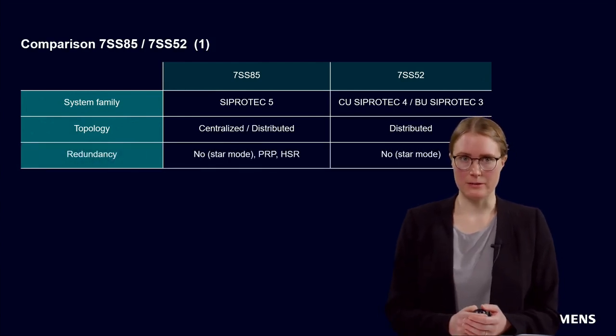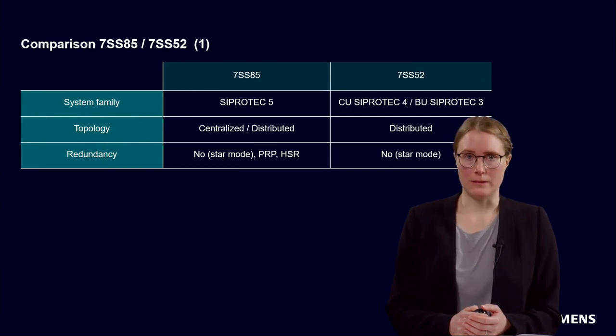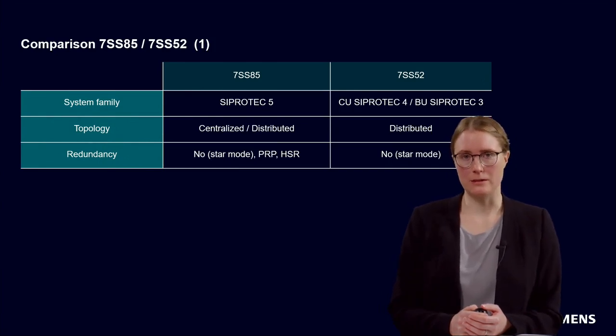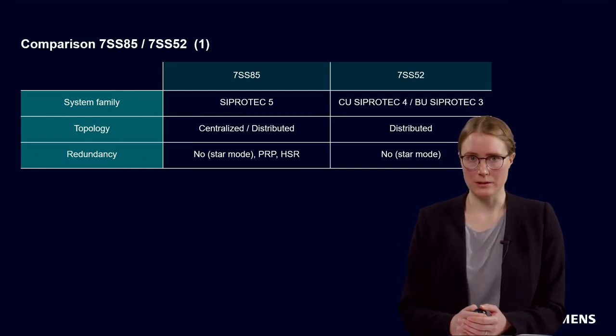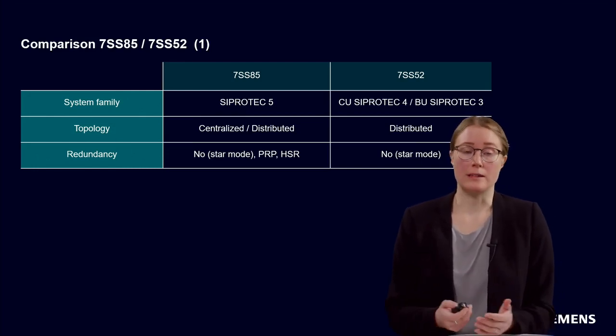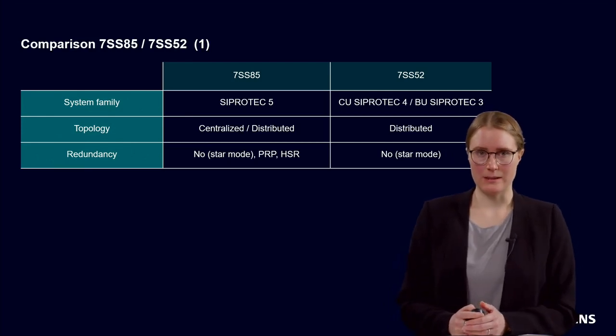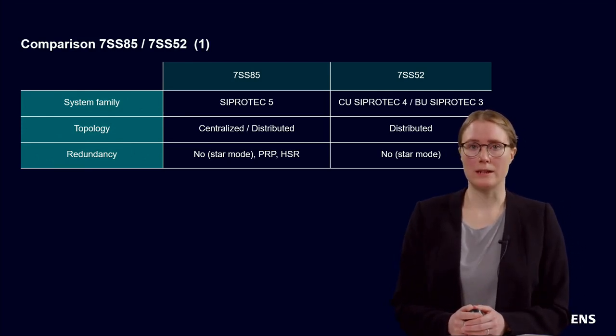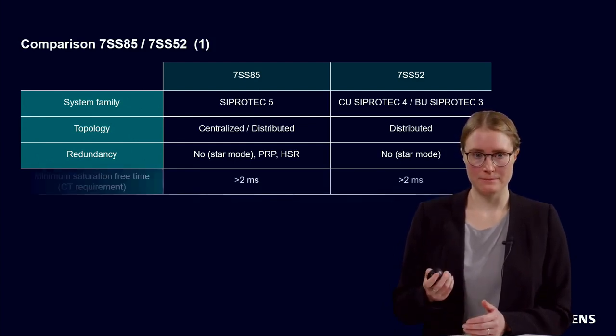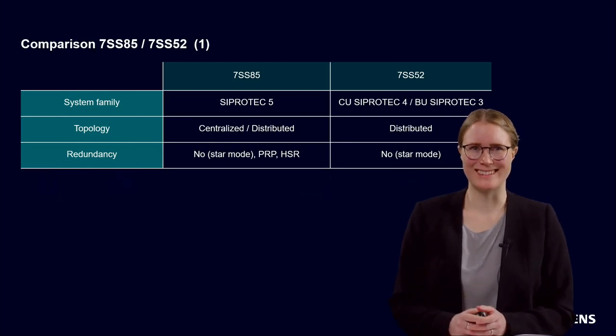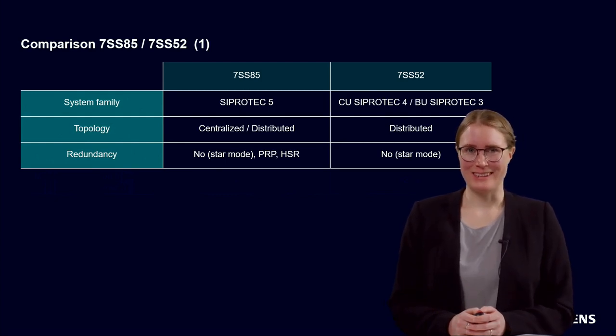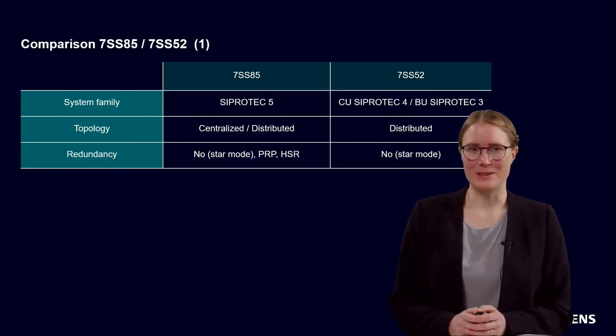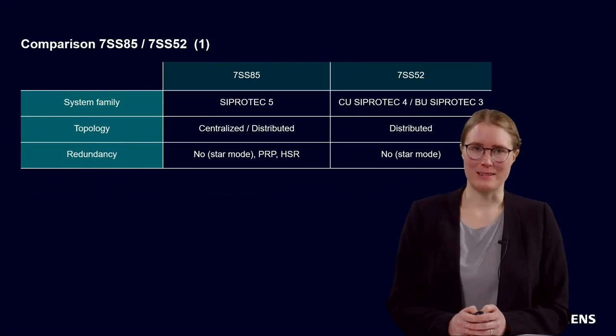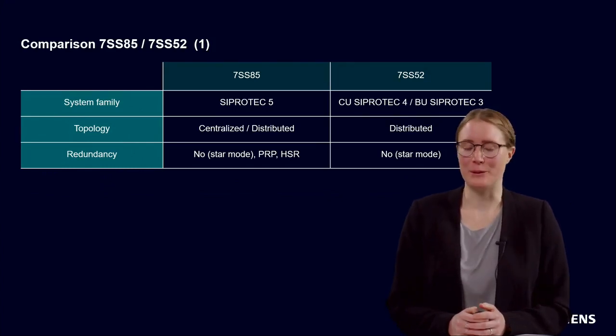If we compare the communication redundancy, we can offer with SIPROTEC 5 redundancy protocols like PRP or HSR. But you can, of course, also use star mode without any redundancy. With the 7SS52, the bay units are always connected via star mode to the central unit. The time synchronization is in SIPROTEC 4 done by the protocol. In SIPROTEC 5, you can use, since version 9.20, the integrated Grandmaster clock. No additional equipment is needed in both cases.